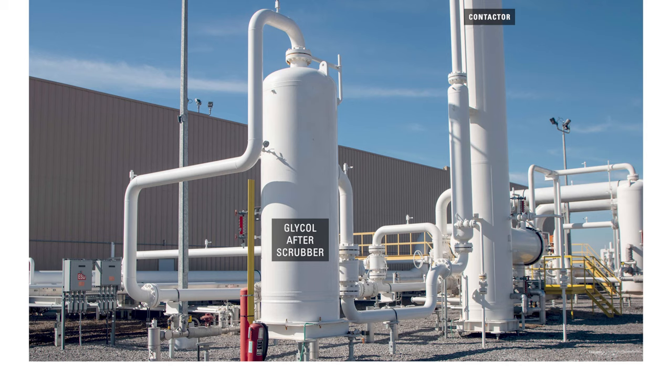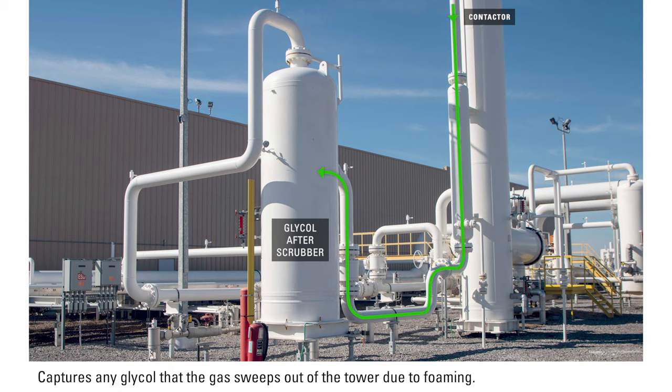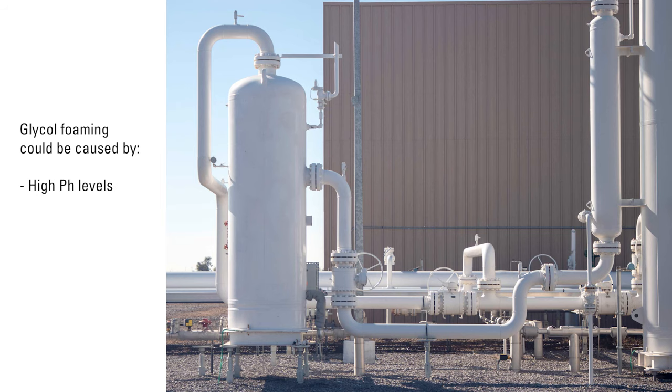The next vessel is a glycol after scrubber. The function is to capture any glycol that the gas sweeps out of the tower due to foaming. This could be caused by high pH levels or a high temperature differential between the gas and the glycol.